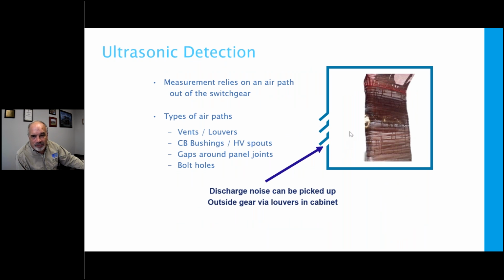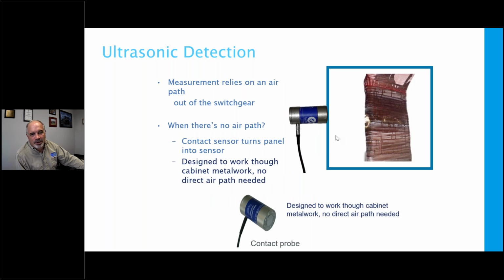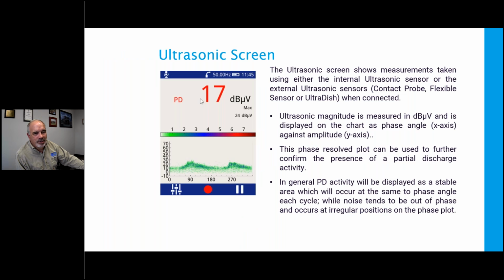Ultrasonic detection through louvers or gaps, that's great. You want to find that. If you don't have louvers and gaps available, you're going to use the contact sensor. I've already talked through that. Here's the ultrasonic screen. Tells me what sensor I'm using, tells me the level. The level's turned red because it's a high level. I've got my algorithm telling me it's PD or noise. I've got my phase resolved plot, and I'm listening. I'm wearing the headphones all the time.